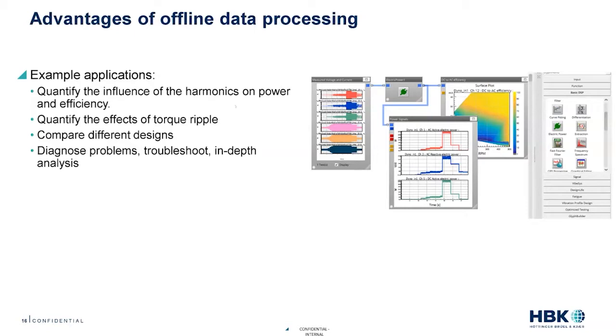By doing it offline, you can find a cutoff frequency, filter, and quantify the influence of those harmonics on your efficiency. You can also quantify the effects of torque ripple, since we collect all this data at a very high sample rate and bandwidth - we see the actual fluctuations and oscillations of the torque signal around a mean value. So we have the ability to quantify that and see its downstream effects in terms of acoustics, vibration, or even durability.